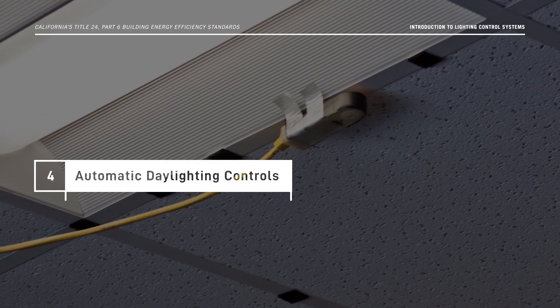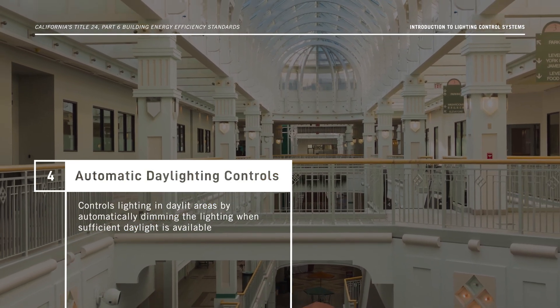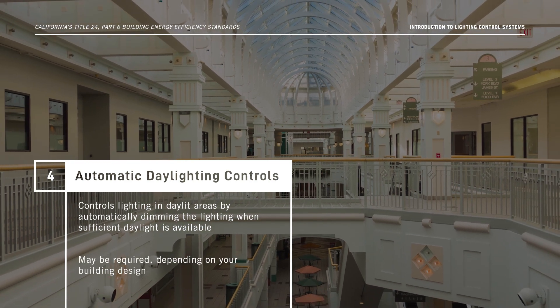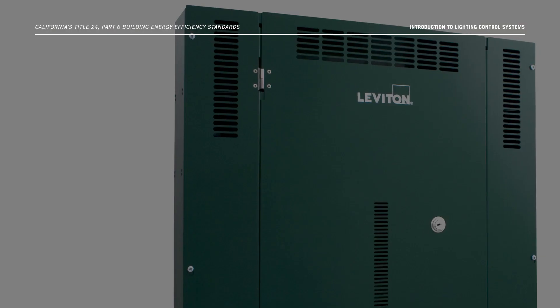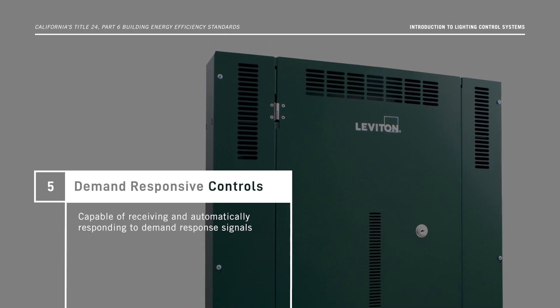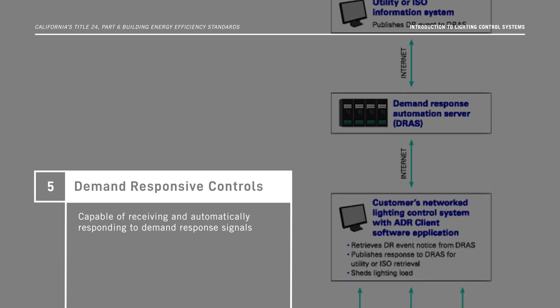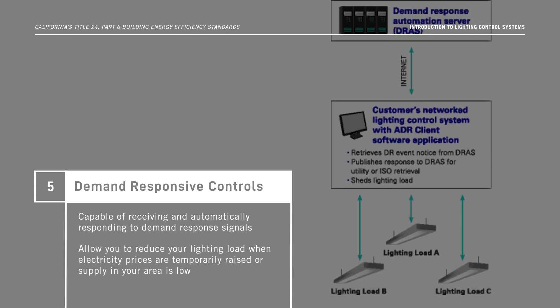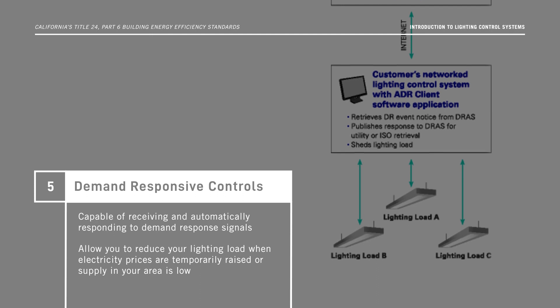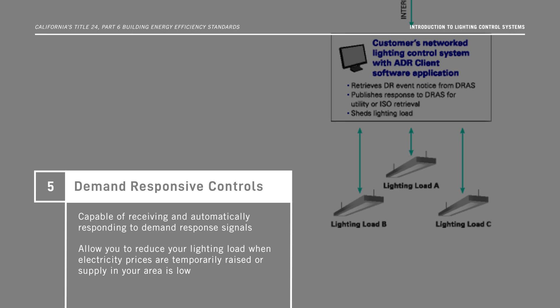Automatic daylighting controls form the fourth layer in a space. They control lighting in daylit areas by automatically dimming when sufficient daylight is available. They may be required, depending on your building design. The fifth and last control layer is demand-responsive controls. These controls are capable of receiving and automatically responding to a demand-response signal sent from a utility or third-party program implementer. They allow you to reduce your lighting load when electricity prices are temporarily raised, or the electricity supply in your area is critically low. These controls have to meet requirements in section 110.12.